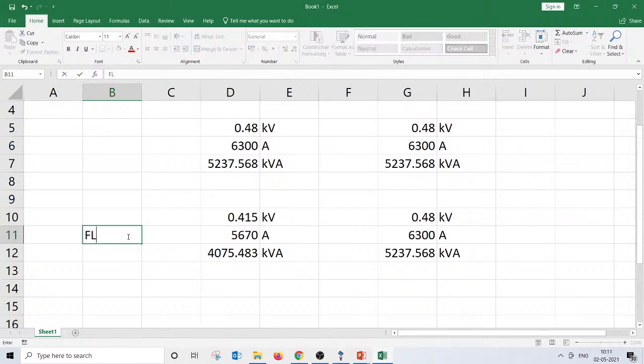No, this is the full load current. I am not really talking about the short circuit current. So at least we can say the full load current of the transformer should be limited to less than the LV circuit breaker rating which is available. So that current is 6300 amps, and you need to consider voltage fluctuation. So you cannot really load up to that 6300 amps.